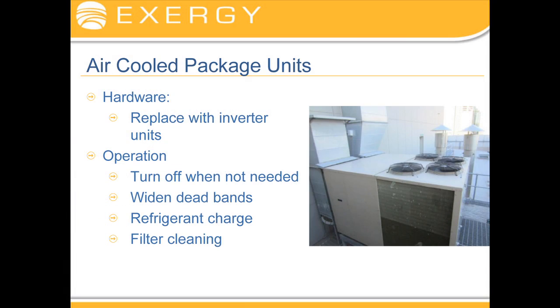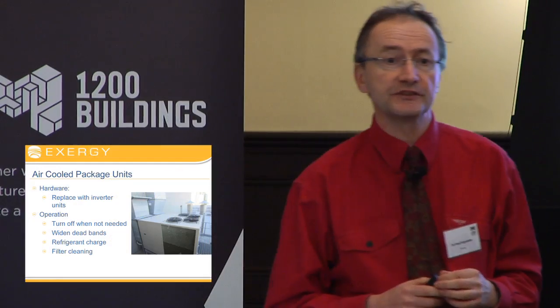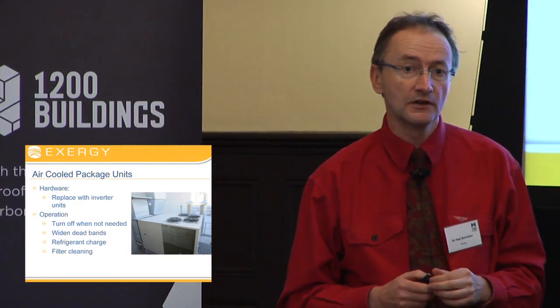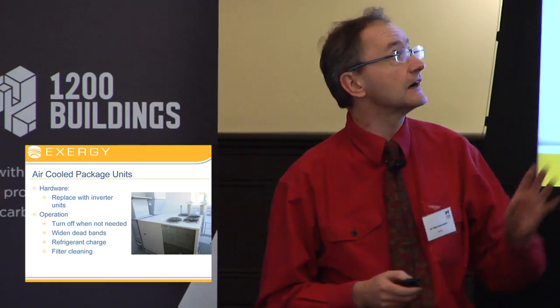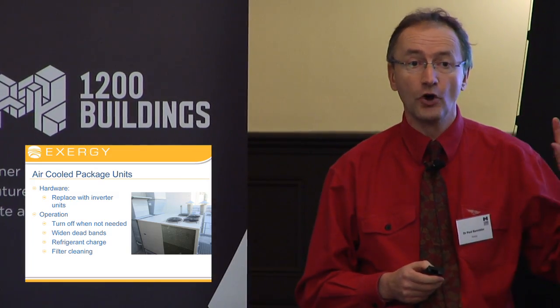Exactly the same issues for air-cooled package units, except that with air-cooled package units, we have inverter compressors available to us, which give us another 30 or 40% efficiency relative to a standard compressor. And so there's some real meat to be had just on replacement.